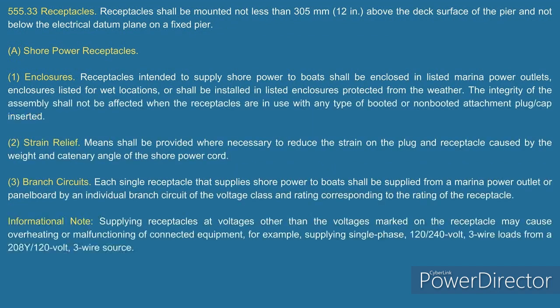Now, let's go a little bit further. If you go in and you look at this, it talks about the receptacles and how you mount them and everything. And when you come down and you start looking at the different things, it talks about the enclosures for shore power receptacles. And look at here: receptacles intended to supply shore power to boats shall be enclosed in listed marina power outlets, enclosures listed for wet locations, or shall be installed in listed enclosures protected from the weather. The integrity of the assembly shall not be affected when the receptacles are in use with any type of booted or non-booted attachment plug caps inserted.